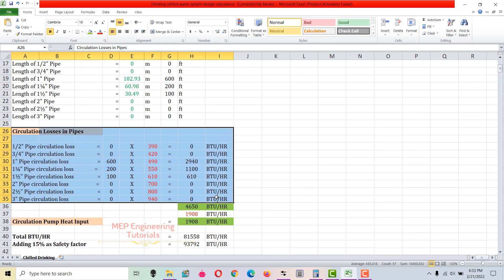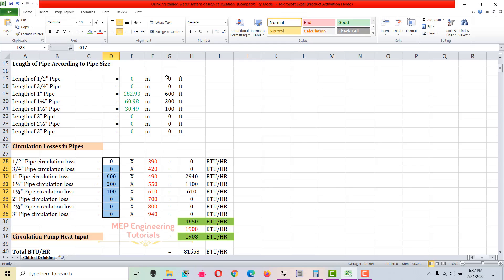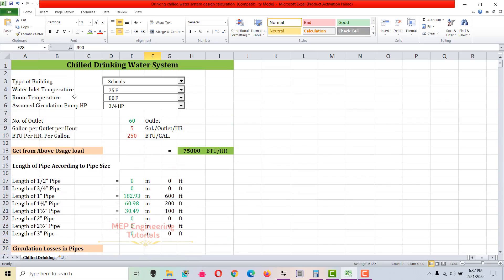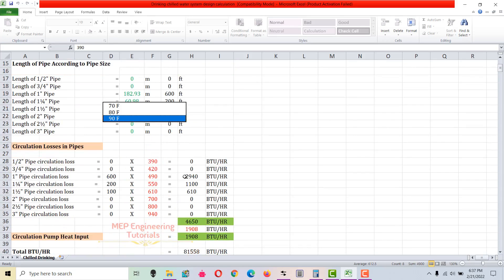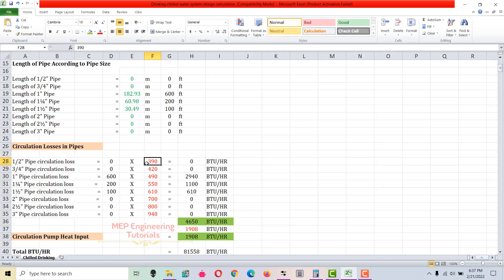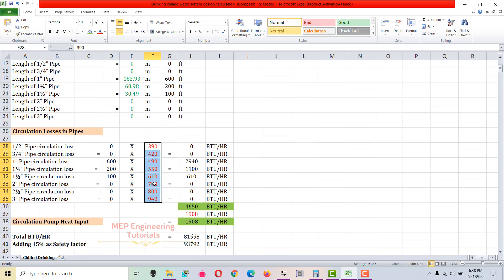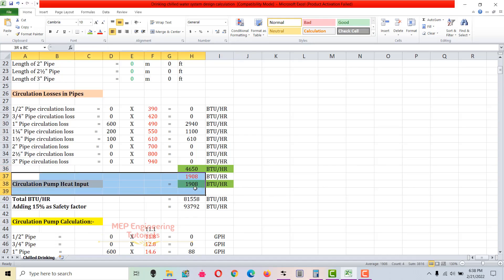Now I calculate the circulation losses in the pipe. I've entered the pipe lengths here — same as above — and these red values are in BTUs per hour per 100 feet of pipe. These values depend on the room temperature selected: 80°F in our case. To get circulation losses, multiply length by the BTU rate and divide by 100 to convert from per-100-foot to per-foot. Total losses calculated here are 4,650 BTUs per hour.